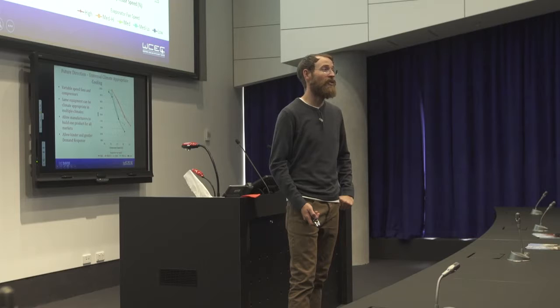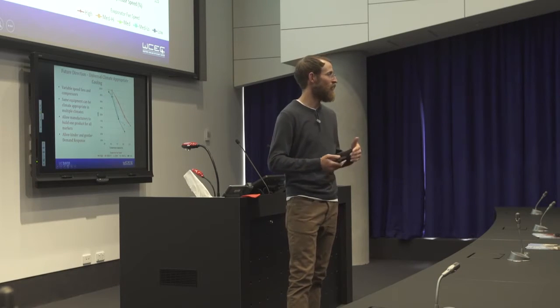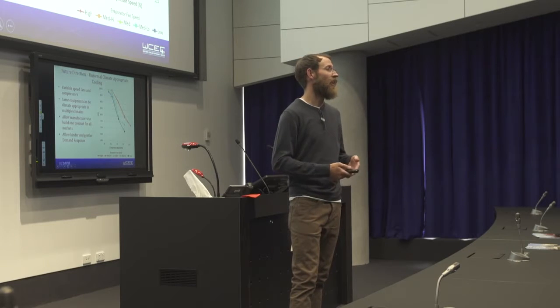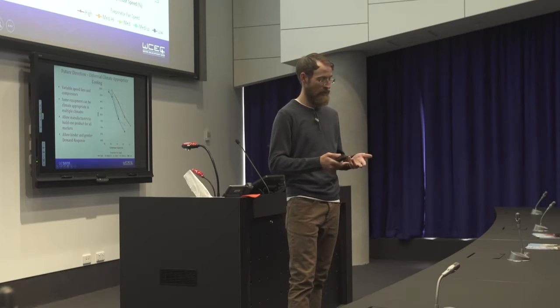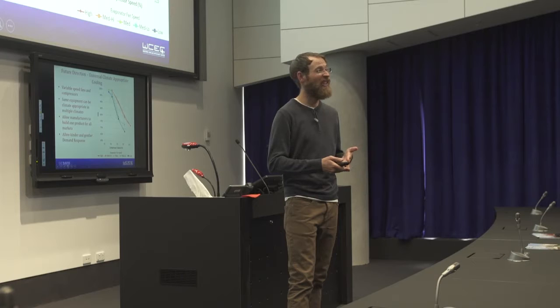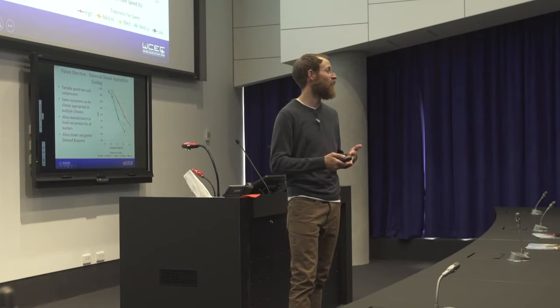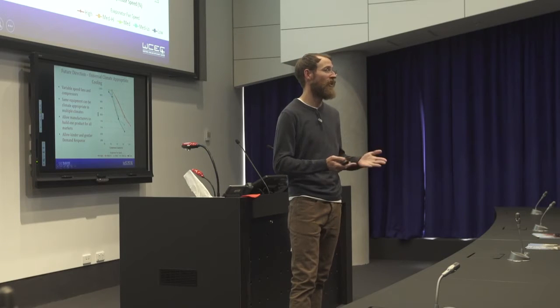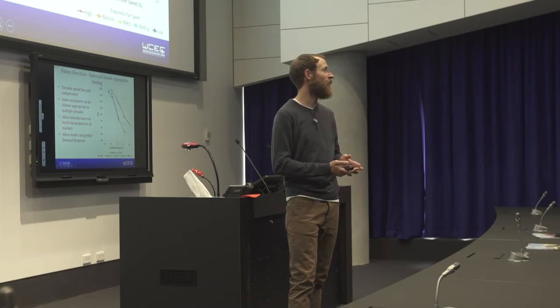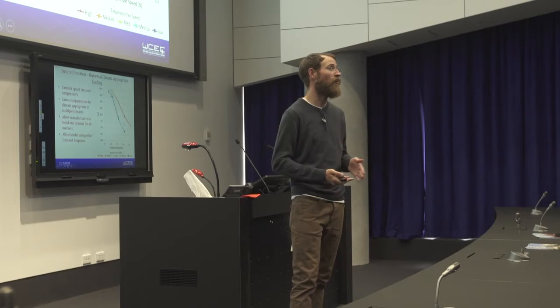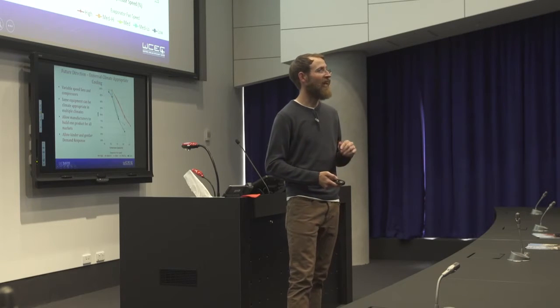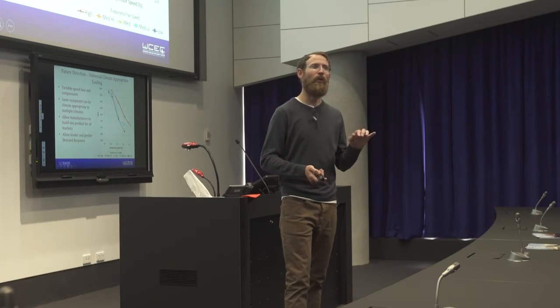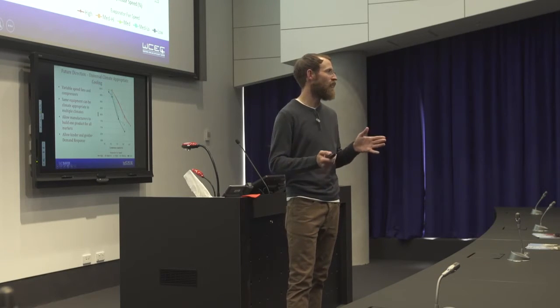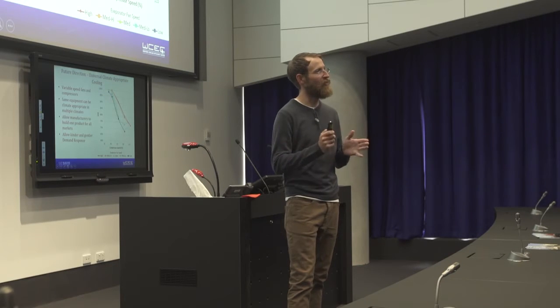Now, a lot of vapor compression systems have been moving towards variable speed, especially including variable speed fans and compressors. Those approaches do improve the cooling efficiency, especially at part load, and they achieve the most significant amount of savings by reducing fan speed during ventilation operation. So all of the periods of the year that you're operating in ventilation only and you don't need to provide cooling, they can reduce energy use by well more than 50%. However, we're showing that if you operate those compressors and fans together in just the right way, you can do some other tweaks and optimization.